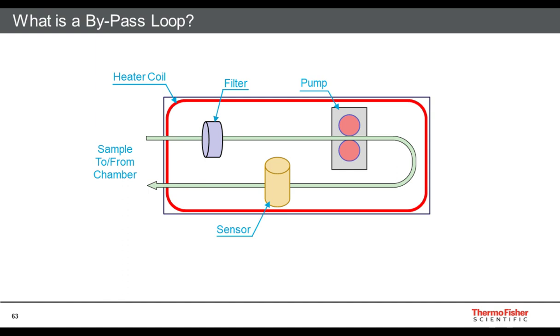What happens here is you can see that there's an arrow that forms a U-turn. That represents tubing coming to and from the incubator chamber. So we're essentially in a box inside the incubator housing, but outside the incubator chamber. This tubing removes an air sample from the incubator chamber where the cells are, passes through a filter to restrict any airborne contaminants, passes through a pump to keep the air moving, and then encounters the sensor, which then reacts to that air sample.